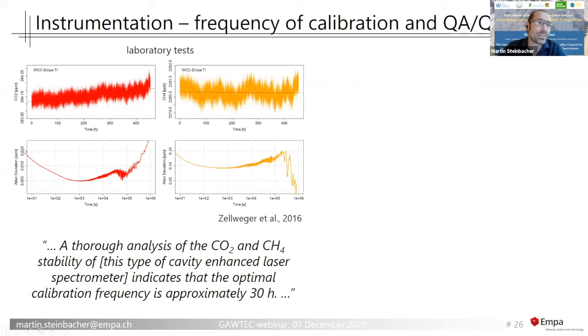In the lower panels, you see the Allan deviation. That's the standard deviation. In a perfect world, this line should come more and more down, because you have more and more data for averaging, and then the standard deviation would become smaller and smaller.